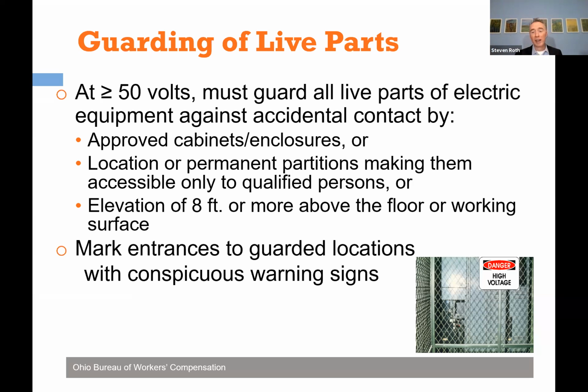That's the best way to handle it, covering all of this equipment. There are also some other provisions where you can have a high voltage room, cabinet, or enclosure where only qualified persons can enter. But if there's still exposure to shock, I have to enter it properly.